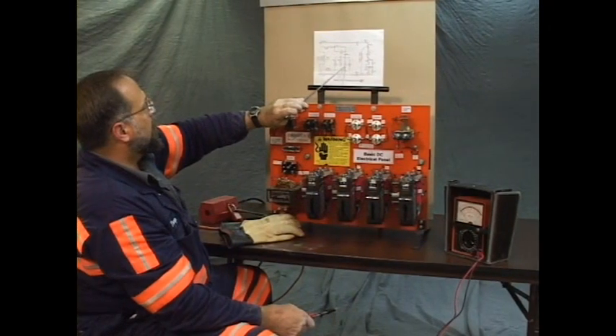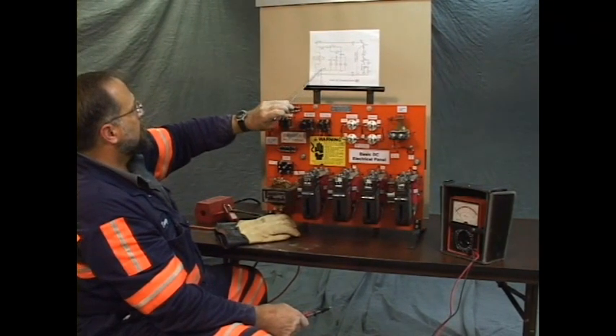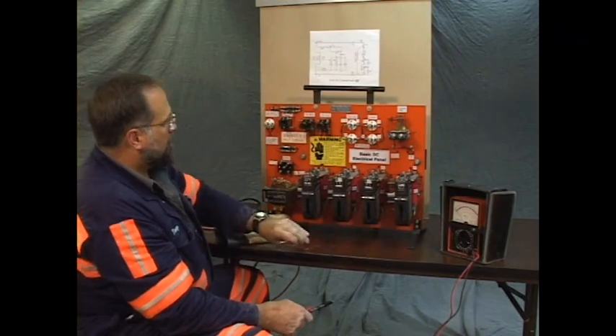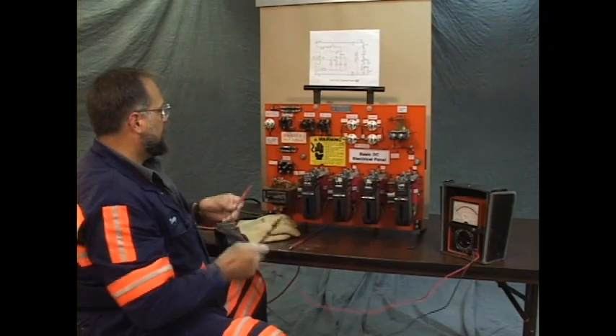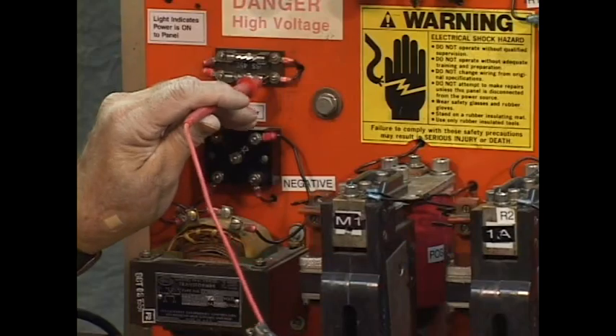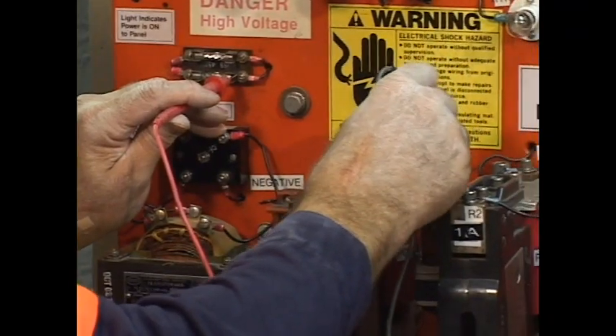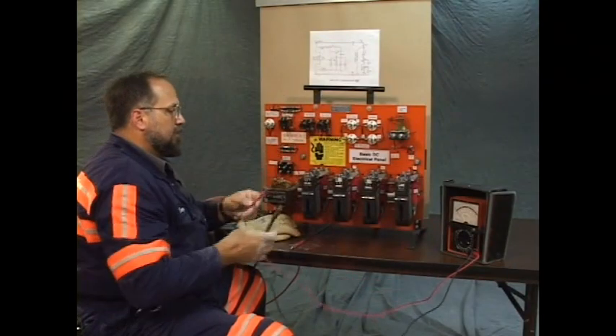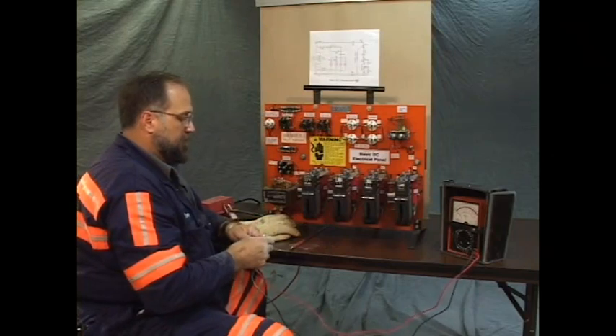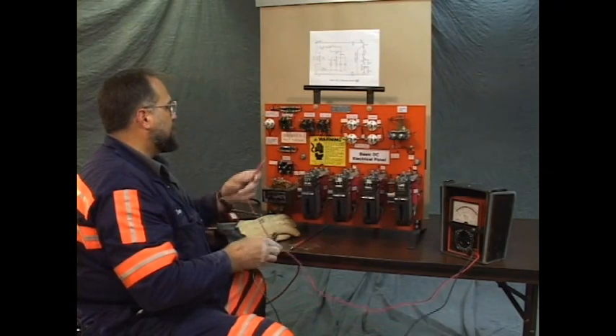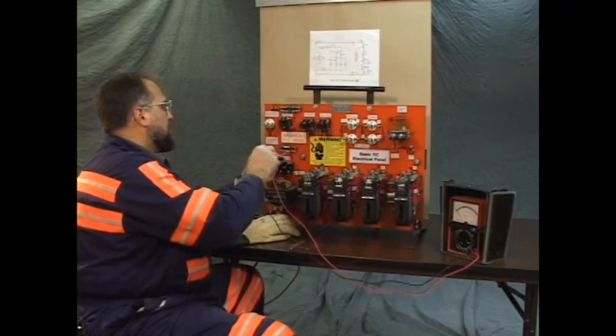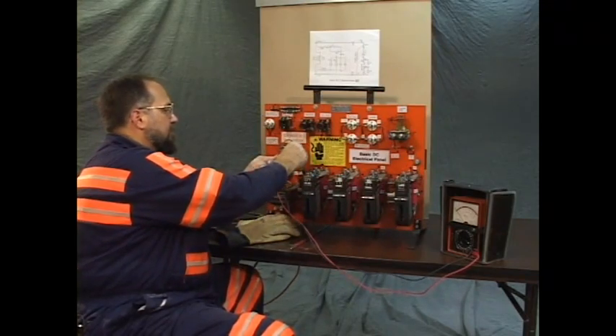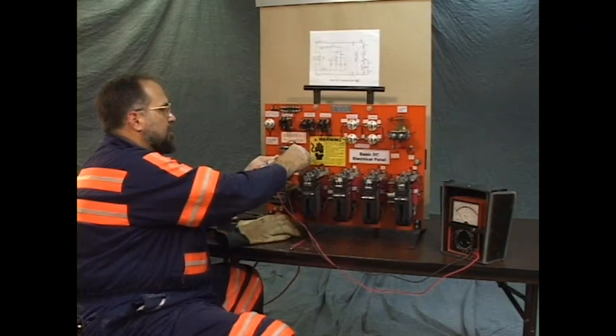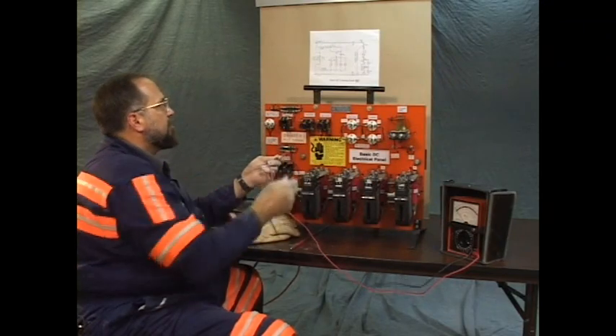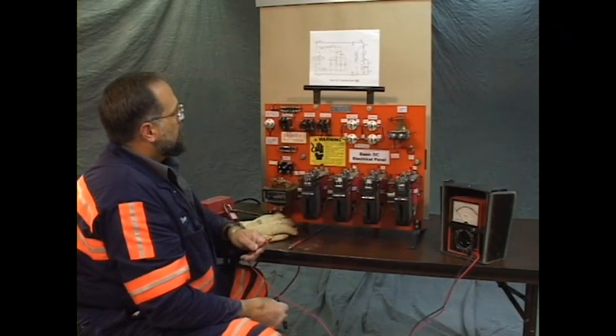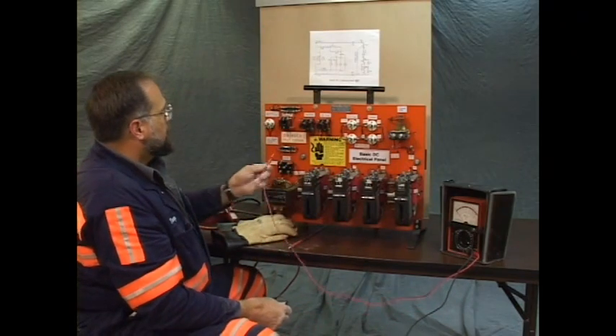So let's check from the negative of M1 to the load side of the negative fuse. That's a good deal easier to reach, this portion. And we don't have it. Let's test our meter just to make sure the meter's good before we call it. The meter's reading correctly. According to the drawing, I should have a circuit from the negative of this contactor coil to the load side of the negative fuse. It's not there. To further check it, let's check another contactor just to make sure.